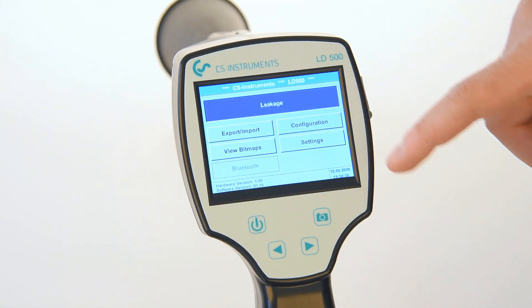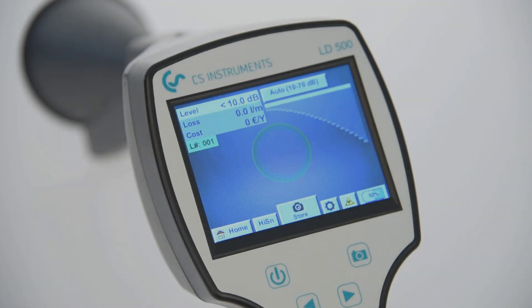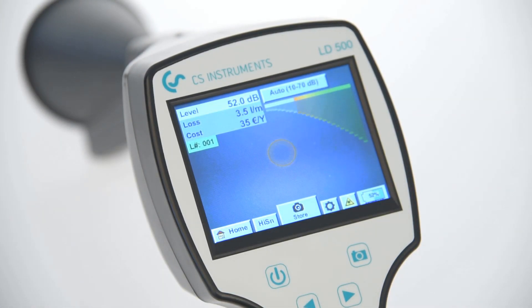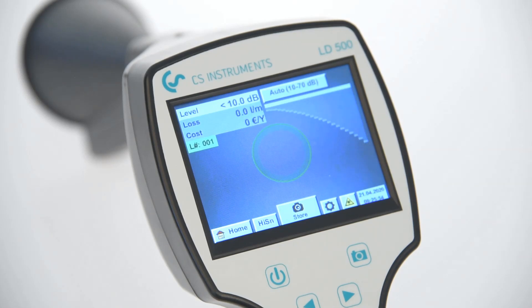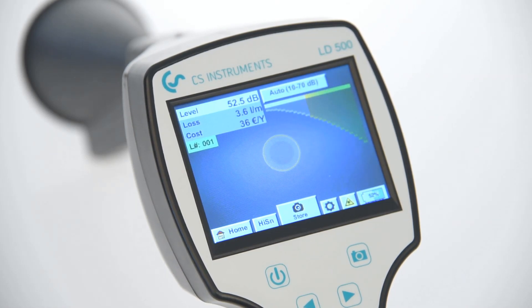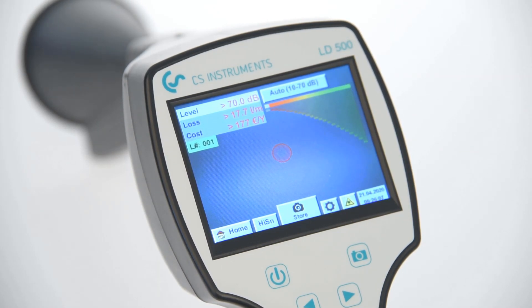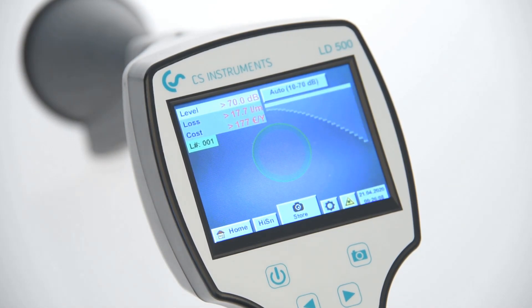In the top left corner of the main screen, the intensity of each leak is indicated. The level indicated is the intensity of each leak measured in decibel. The loss indicated is the amount of air which is lost at this particular leak location. The cost indicated is equivalent to the savings potential if the particular leak were to be repaired.